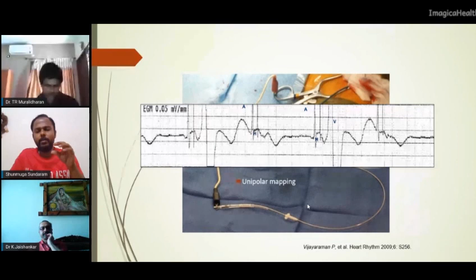Once you connect it, either in the EP system or in the programmable system analyzer, you'll be able to see 3 deflections. The first is the A deflection, the second is the His bundle deflection, and the third is the ventricular deflection. Here you have to place the lead in such a way that your A electrogram is very small, and you have a big ventricular electrogram and a decent looking His bundle electrogram. This is very important. A large A, as shown in this picture, should be avoided because it is going to produce atrial oversensing during follow-up. So you have to have a very small A, probably in the ratio of 1:5 to the ventricular electrogram, and a decent looking His bundle electrogram.